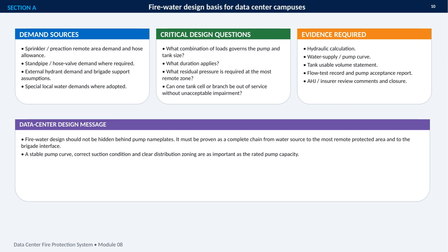The design also needs evidence, not just equipment labels. That evidence includes the hydraulic calculation, water supply and pump curves, a statement of usable tank volume, flow test results, the pump acceptance report, and documented AHJ or insurer comments with closure. The complete chain from the water source to the most remote protected area and the brigade interface must be proven. A stable pump curve, proper suction conditions, and clear distribution zoning matter just as much as the pump's rated capacity.